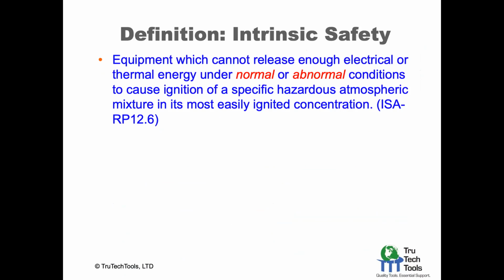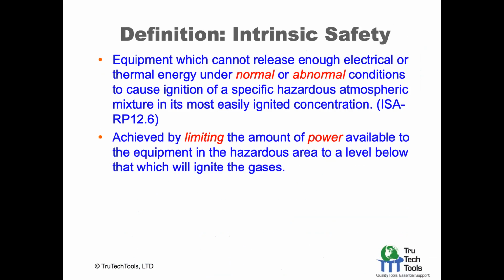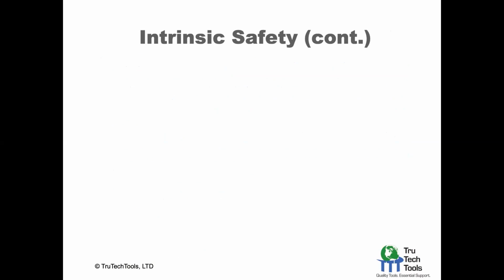Okay, so that's what you're measuring: basically, prevent hazardous atmospheres, by having a measurement of the concentration of gas. This is achieved by limiting the power. This is by design, the power that's available inside the equipment, inside the unit in your hand, which could ignite the gas. So intrinsic means by design, but you, the user, must use it as it's designed. That's why we're going through this course today, so you understand how to use it.